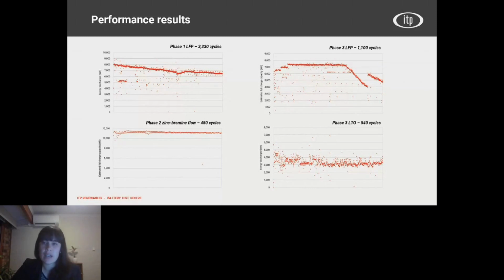The last graph here is one of our phase 3 batteries, which doesn't have communications from the battery BMS to the inverter, meaning the inverter is required to estimate the battery state of charge. We found it really difficult to get this particular battery and inverter working optimally together, which is indicated by the large spread of energy discharged per cycle, as well as the low amount of energy discharged per cycle compared to its nominal capacity. Since installing this battery, the manufacturer has confirmed that it actually doesn't support this inverter as compatible.